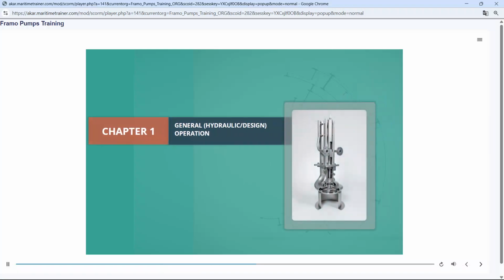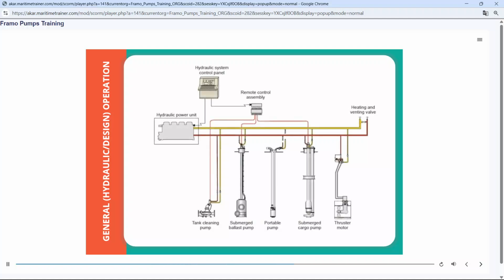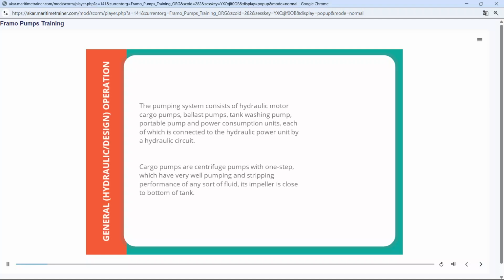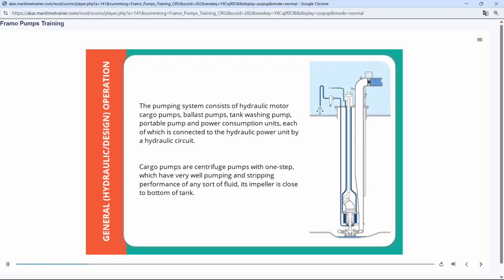Chapter 1. General, Hydraulic and Design, Operation. You can see the industrial design figure of Framo pumps for analyzing parts. The pumping system consists of hydraulic motor cargo pumps, ballast pumps, tank washing pump, portable pump and power consumption units, each of which is connected to the hydraulic power unit by a hydraulic circuit. Cargo pumps are single-stage centrifugal pumps, which have very good pumping and stripping performance for any sort of fluid. Its impeller is close to the bottom of the tank.